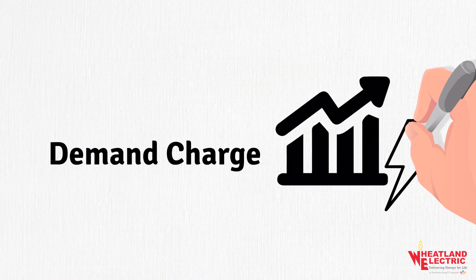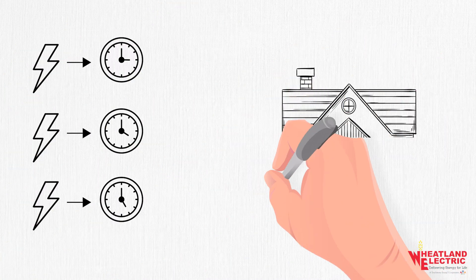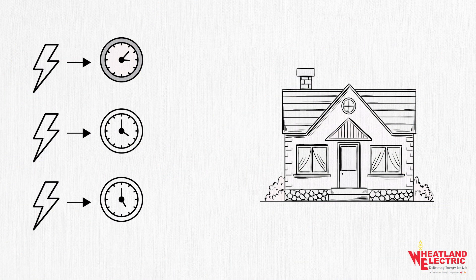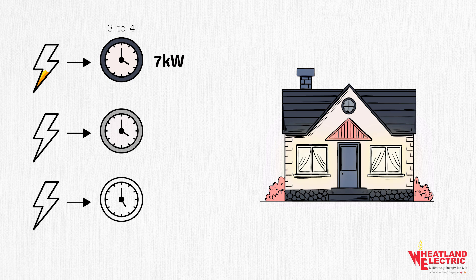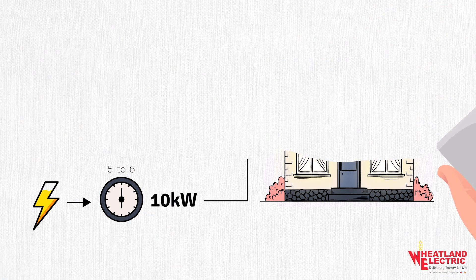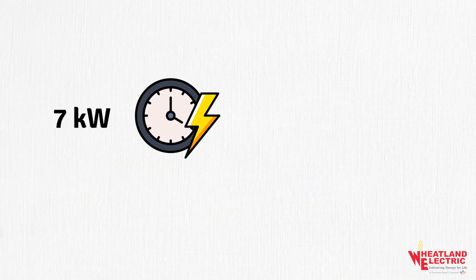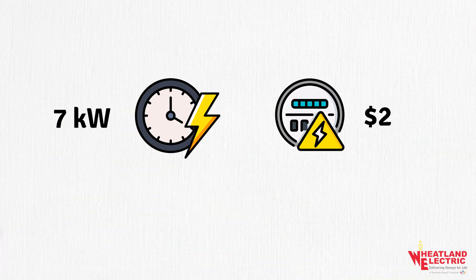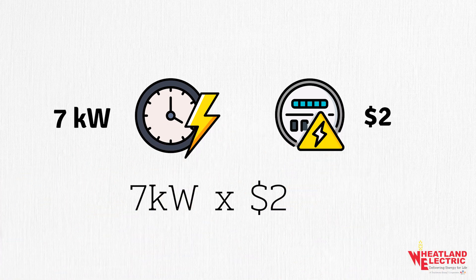The demand charge is calculated differently, and it is something each member can control. It is determined by the maximum demand of energy at any point within the billing cycle, multiplied by the applicable rate for a member's specific rate class. For example, if seven kilowatts were the highest demand for the billing month at a cost of two dollars per kilowatt, your demand charge would be 7 kW × $2.00 = $14.00.